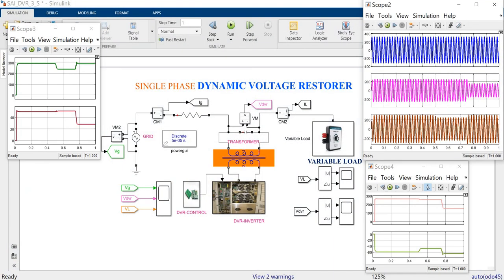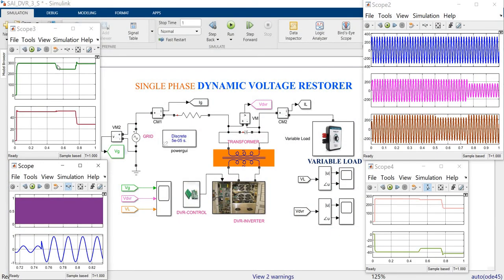I am going to run this system once again. During the time of 0.5, I am creating the sensitive load change operation, so a voltage sag is created. At 0.75, I am going to change the DVR angle — the angle is varied. During that time, the pulse is also varied in this session, and it will compensate the voltage at that point.